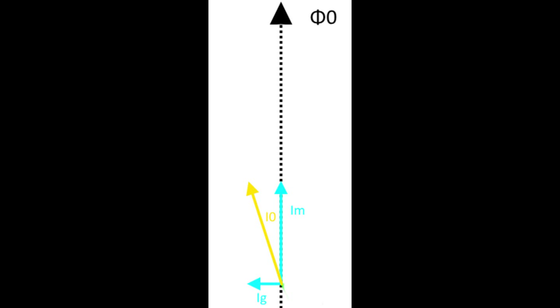Now, if we want the total primary current, we also need to add the zero load current together with the compensation load current to get the total primary current. Also note, the compensating load current is 180 degrees phase shifted relative to the secondary current.